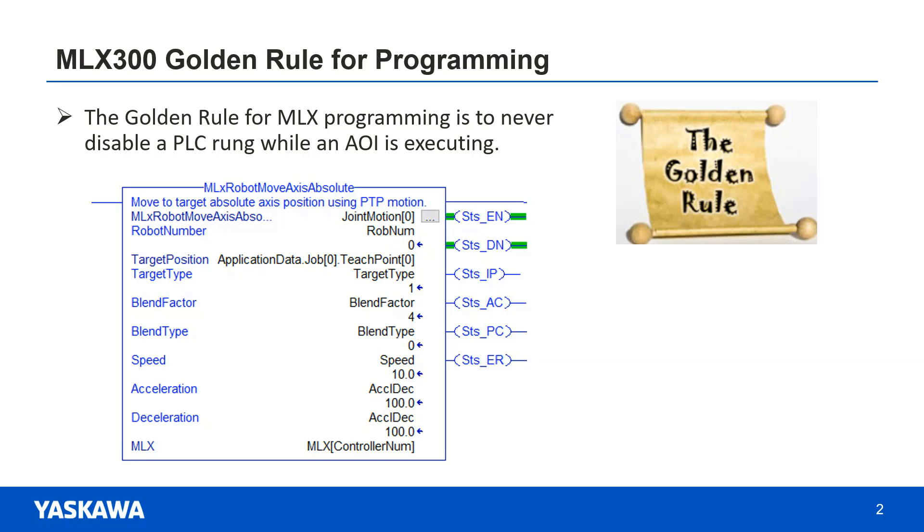When the done bit comes on, this rung can be disabled and the motion will still execute okay. However, there will be no feedback from the other status bits of this AOI such as the alarm bit and the process complete bit. The PLC won't know when the robot reaches this position.